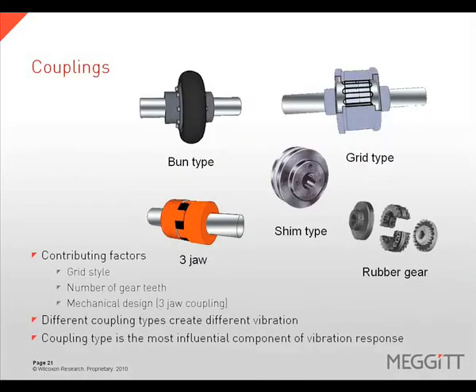Coupling type can be a major contributing factor to the vibration response of misalignment — different coupling types will create different vibration responses. A bun style coupling may exhibit the traditional 1 times or 2 times vibration response. However, for a 3 jaw coupling, the 3 times vibration is the best indicator of alignment condition. Grid style or gear couplings will vary depending on how many grid elements or gear teeth are in the load zone.